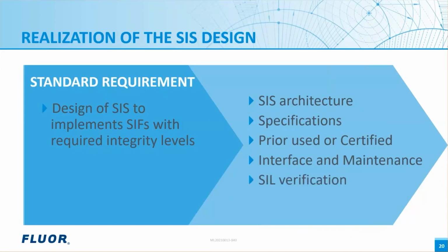SIL verification is an important task to check that the SIL targets are met with the procured devices. What do you do if the targets are not met? Adjust the proof testing or partial stroke testing frequency, and of course, that should be to a practical duration, or modify the SIF architecture and repeat these steps until the SIL target is met. Lastly, testing basically involves the factory acceptance test to prove the design requirements are met.